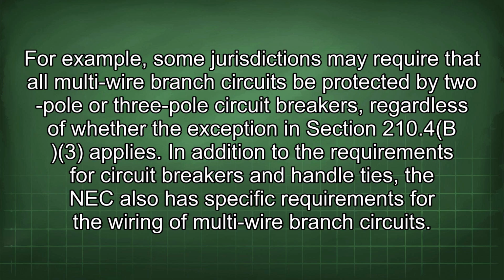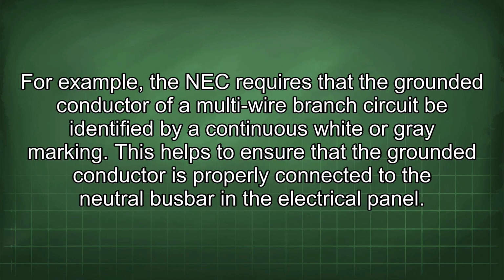In addition to the requirements for circuit breakers and handle ties, the NEC also has specific requirements for the wiring of multi-wire branch circuits. For example, the NEC requires that the grounded conductor of a multi-wire branch circuit be identified by a continuous white or grey marking. This helps to ensure that the grounded conductor is properly connected to the neutral busbar in the electrical panel.